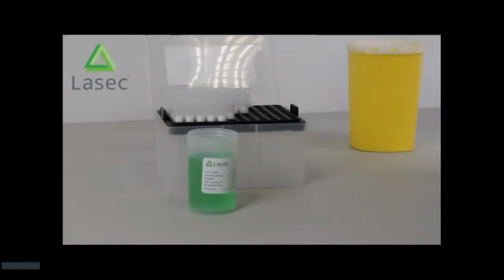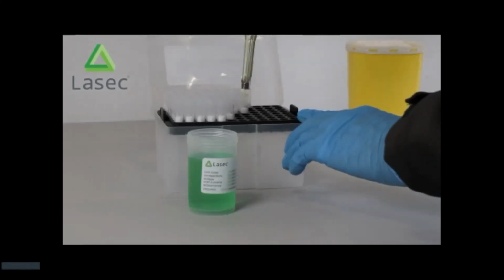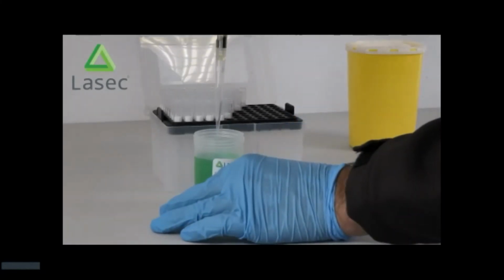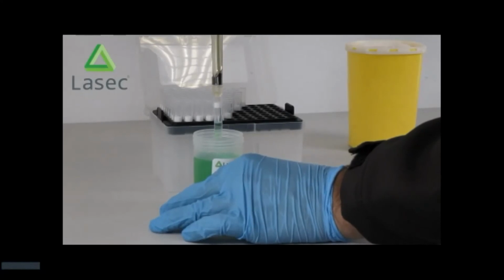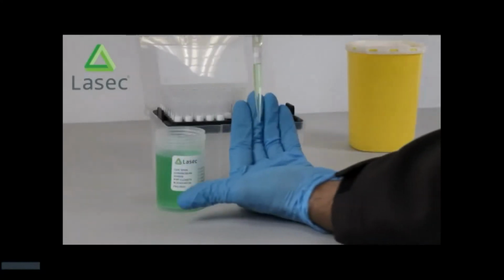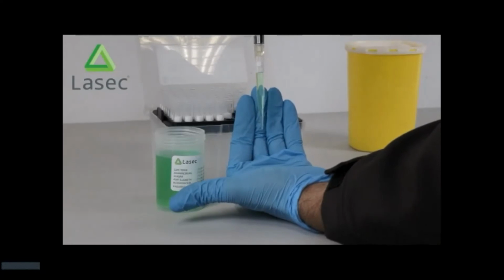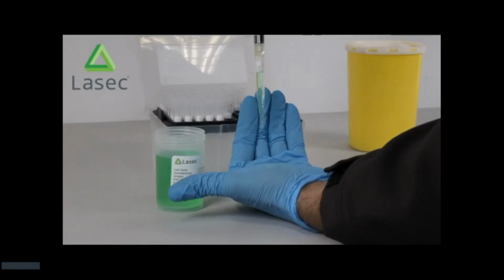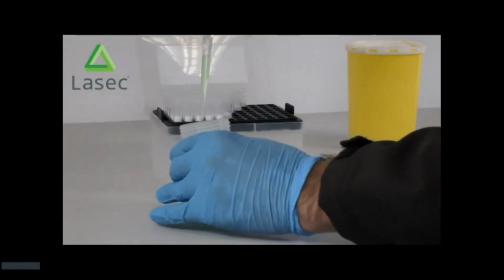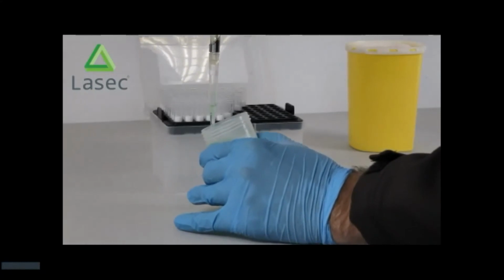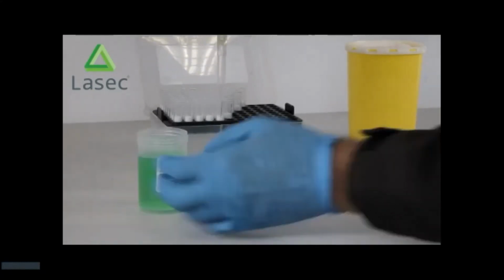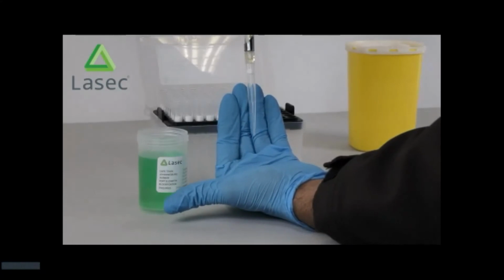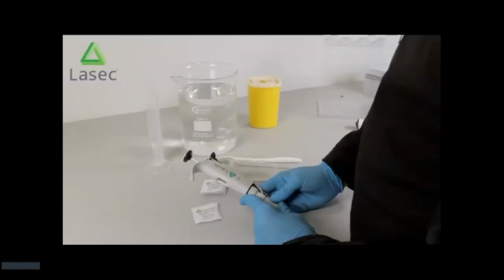The next illustration is going to be a leak test, and this is on a 1 ml or 1000 microliter pipette. Like I said, with the 1000 microliters, you can just simply aspirate that solution and hold it there for a couple of seconds and observe if there is any dripping or leaking. If you were using a volatile solution, for example, you would have instantaneously seen that droplets were forming at the base of that tip. Again, use a different pipette completely because an air displacement pipette is not suitable.